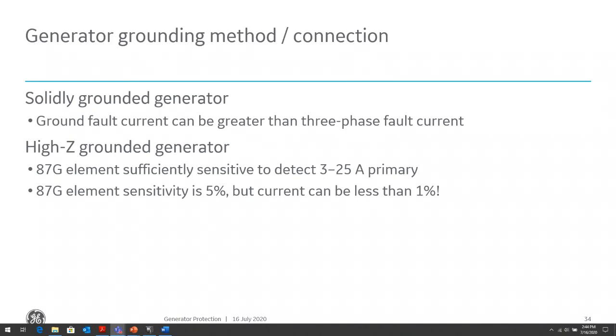We'll talk about them in the next couple of slides, but there are many methods for detecting ground faults. So what you need to do is know what type of grounding method you're going to be using, and you need to choose it wisely. Is the generator important to the process? Do I need to high impedance ground it, or can I solidly ground it and get away with just using a ground overcurrent relay?